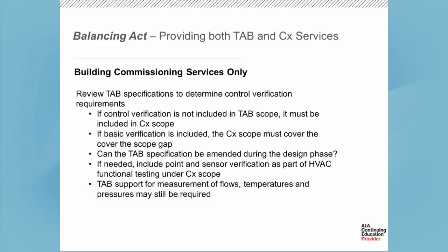Hopefully that's done during the design phase or pre-bid phase, so there's no overlap in the bid process. What we advocate, and have found to be most valuable, is to try to include the point and sensor verification as part of the test and balance scope. But if for some reason that's not possible to put in the TAB specification, it's very important that piece is picked up by the commissioning provider.